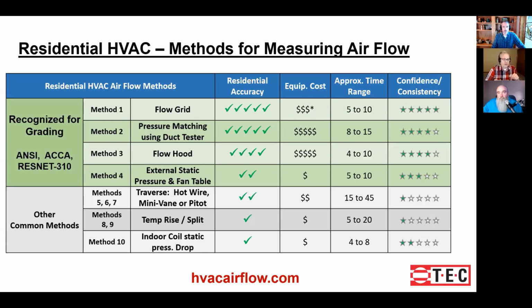But as soon as the blower wheel or the secondary heat exchanger or the evaporator coil starts to get dirty, it doesn't match the factory anymore, and that relationship between the pressure drop and the flow starts to change. It's like the calibration of that method has changed. And so normally it's a good method on a new system when you're installing it. Old systems, it's very dicey.